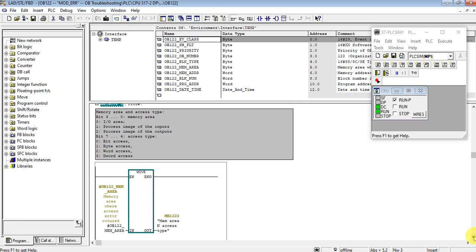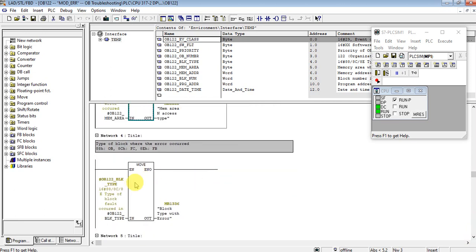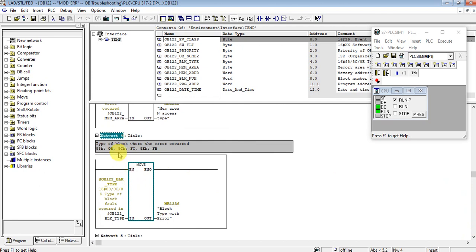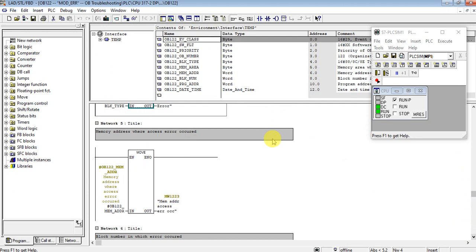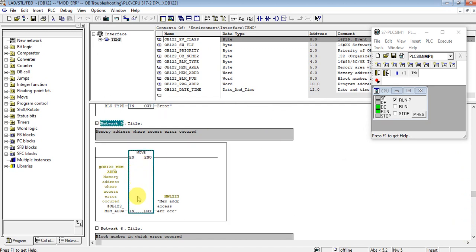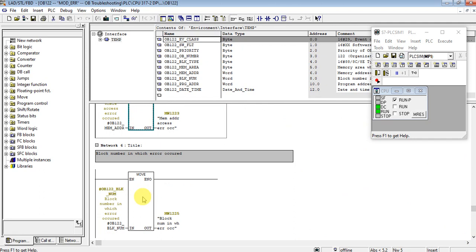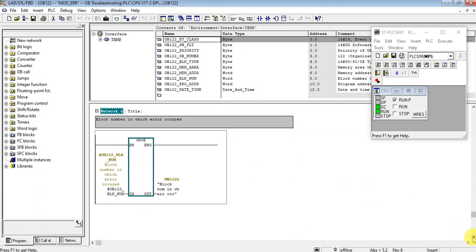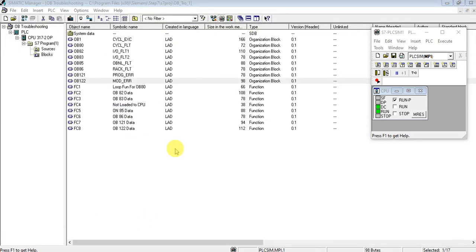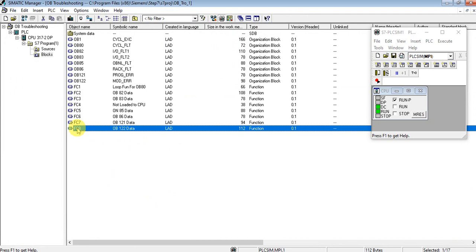On network 4, it will show the type of block — whether it is an OB, function, or function block. If it is 0x88 it is an OB; 0x8C indicates a function, and 0x8E indicates a function block. This also tells us the block number that has the error and the memory address.